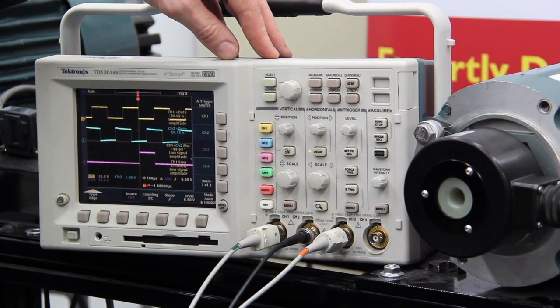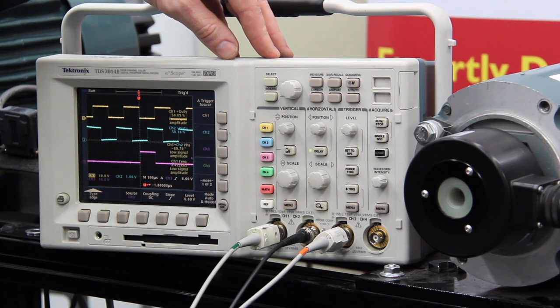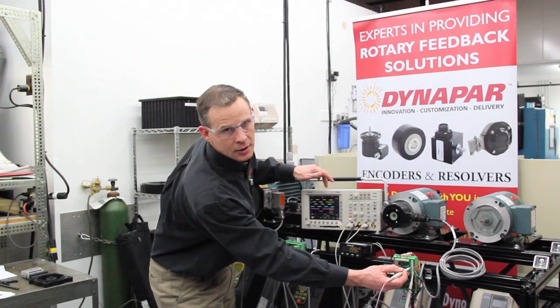In the close-up you'll be able to see that we have both duty cycle, phase relationship, and the frequency output displayed. Each of those are also an indication that the encoder is working properly.